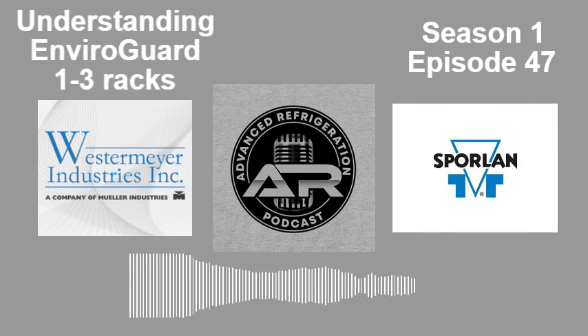This goes for any rack. If you've never been there, you don't know what it is. Look around, look for the Enviro-Guard signs. Even Zero Zone, and like I said, Hill Phoenix has these. I always trace out my piping when I'm looking at something new. If I've never been to a store before and I've never been in the rack room, and I'm there for something more than a fan motor out, I'm going to go in there and look around.